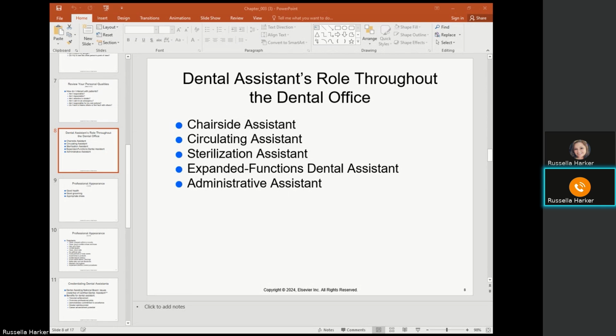making sure that all of the cleaning solutions are being switched out effectively when they need to be. Like the ultrasonic solution only needs to be changed once a day, but more often if it becomes cloudy. So they may be changing that more often. So anything that needs the maintenance part of it in the sterilization area, the sterilization assistant would take responsibility for that.